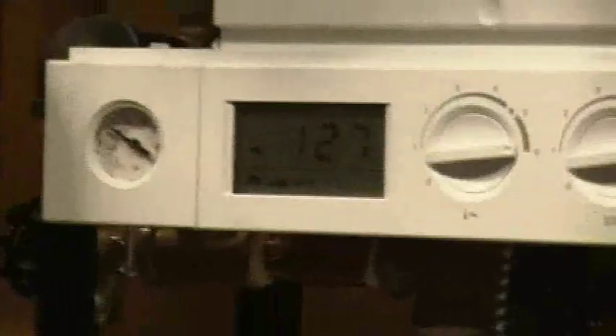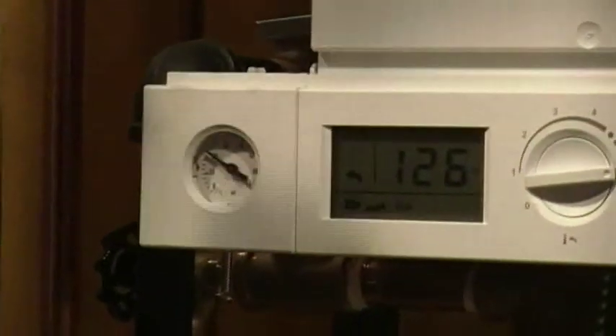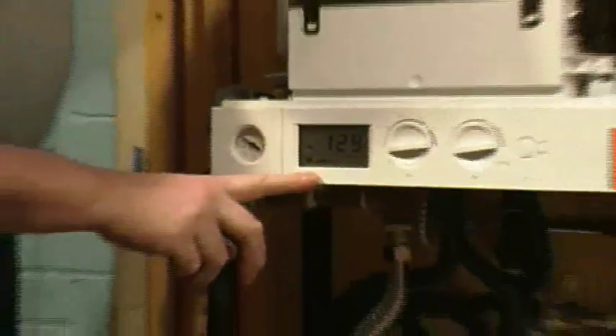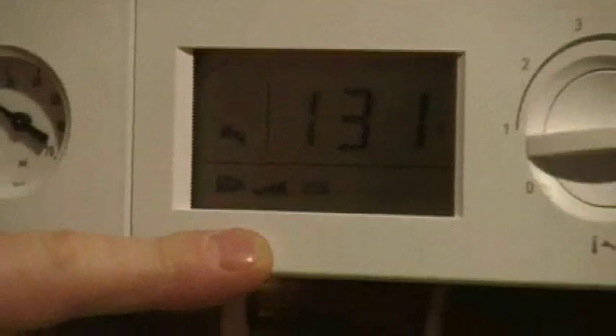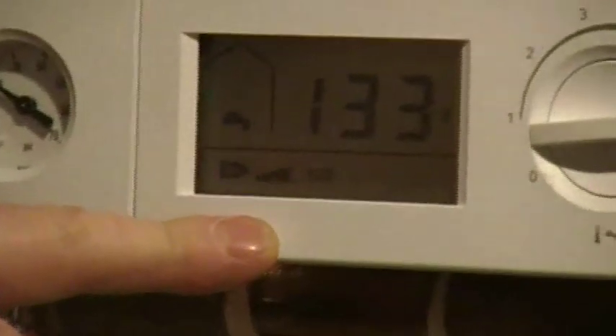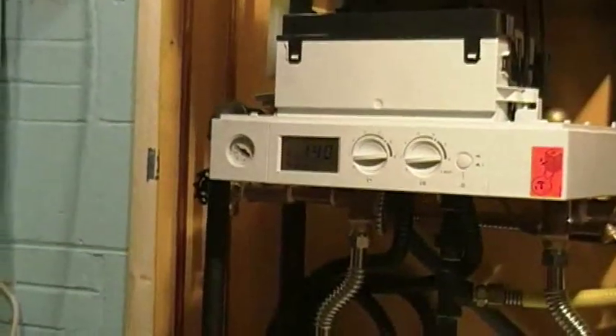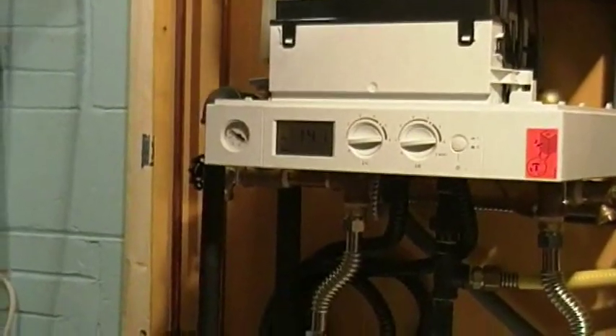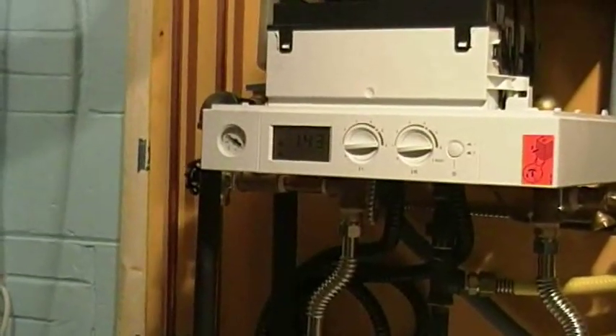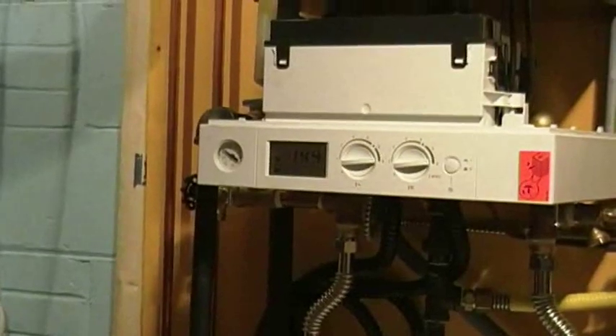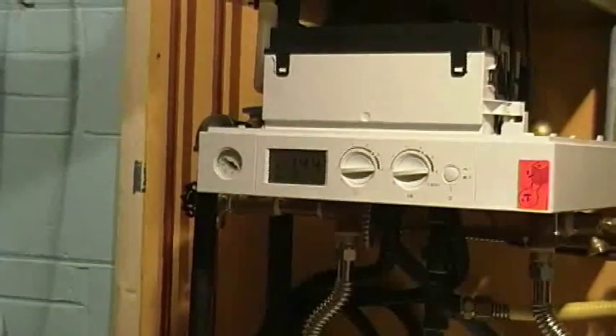And now the boiler is ramping. It's speeding up to meet the demands of the hot water, and it will eventually end up in high fire, and it is actually at high fire right now. So as the boiler accelerates, this is what the actual temperature of the water going out of the heat exchanger is at this point in time, and the domestic hot water is also quite hot at this point. We've just hit about 143 degrees Fahrenheit, which is the actual temperature of the boiler water, not the domestic water.